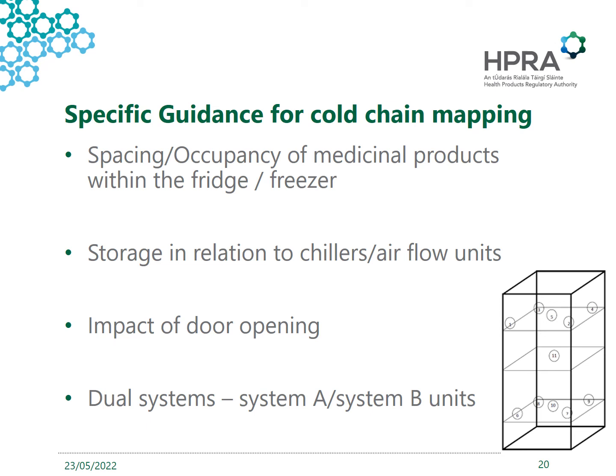We also need consideration in relation to the storage of medicinal products in proximity to chillers or airflow units. Naturally, if there's a chiller above the storage area, this area will be colder than the rest of the storage unit. Therefore, it's expected during the mapping study that there are definitely temperature monitoring probes to show that the required storage conditions are maintained. It may be that it's not appropriate to store products in these areas, in which case we'd expect to see signage put up and documented within the QMS.